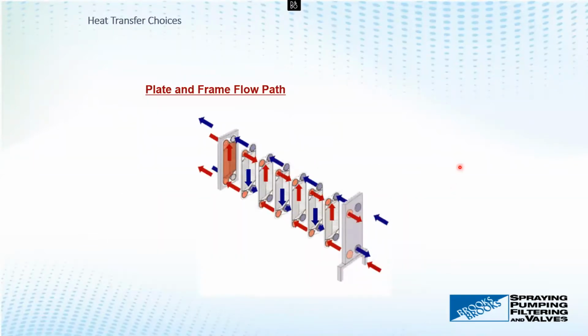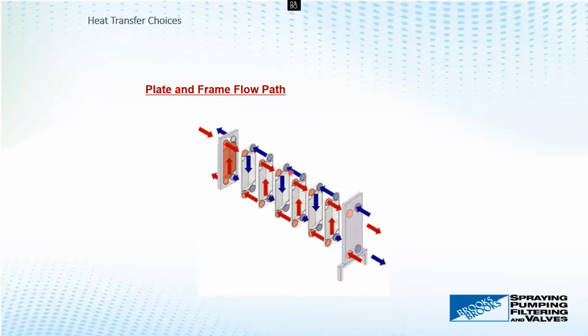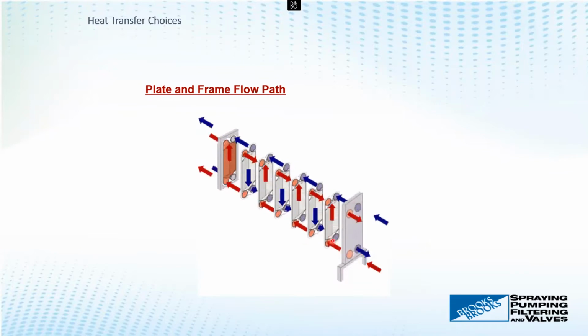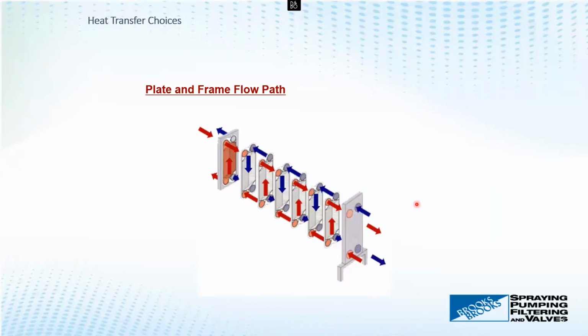And then we talked at length about how plate and frame heat exchangers do not go serpentine through the exchanger. They're header systems. So the inlet of the cold at the top, inlet of the hot at the bottom fills the entire header. And then on each plate pair, it goes up once and then out once. And it's a counter-current flow, so they're going directly opposite each other. And that again is also the most efficient way to heat exchange.